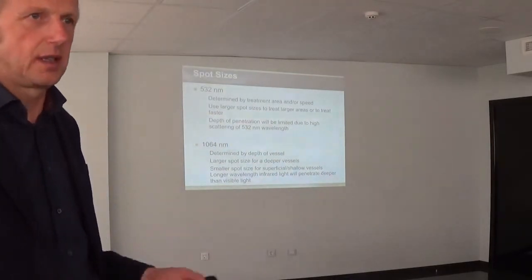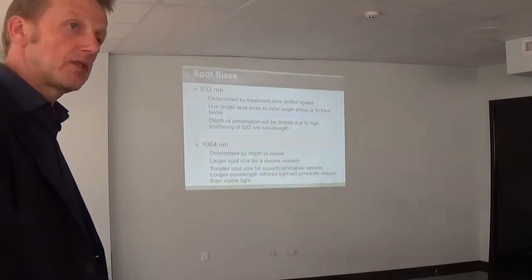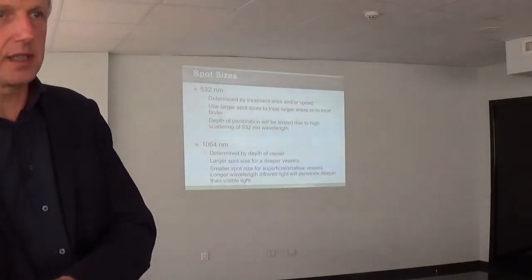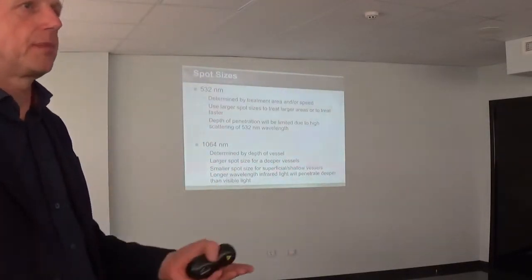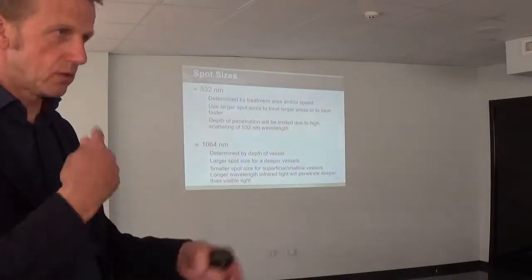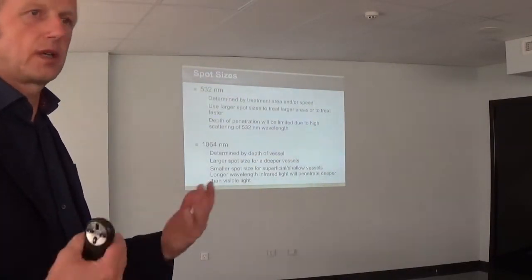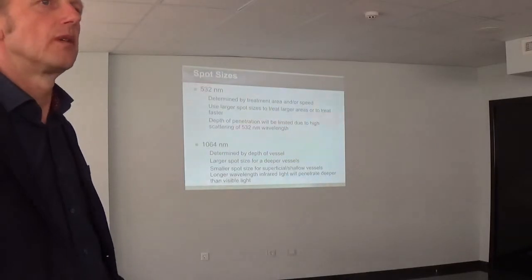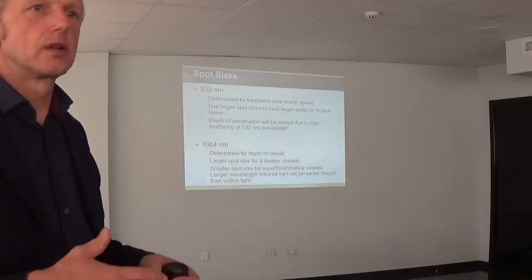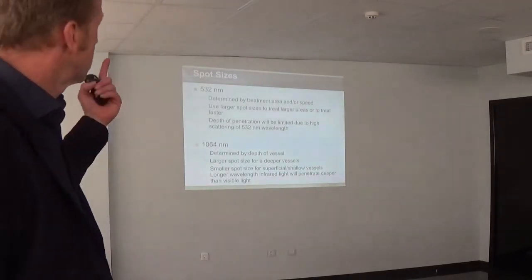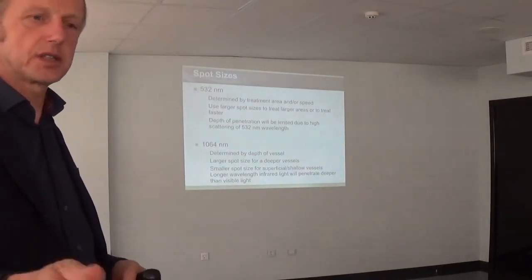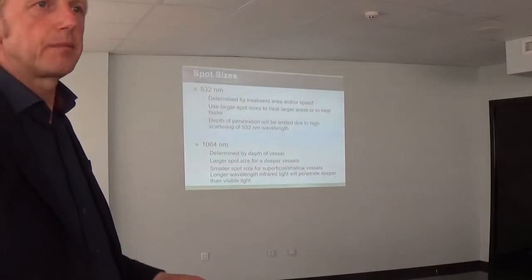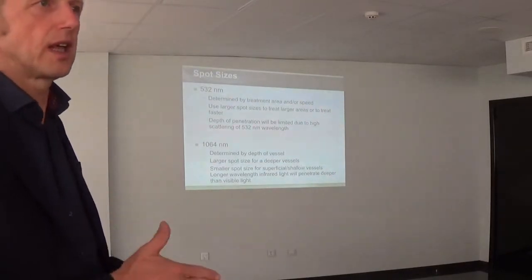deteriorate, so it will not be useful anymore. So it needs to be filtered out and replaced by a new dye. And that's what it's called, the filter plus the dye kit. And after so many pulses, like 5,000 pulses, you need to buy a new dye kit. So here in the XLV there is no consumable, there is no service cost, because it's all solid state technology. The wavelength of the 532 is created by just diverting the Nd:YAG beam through that KTP crystal, and that makes it from infrared to green light.